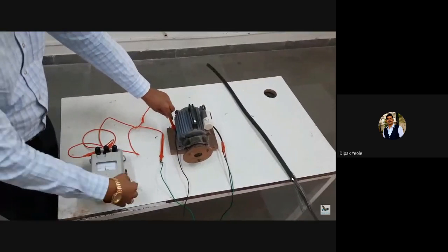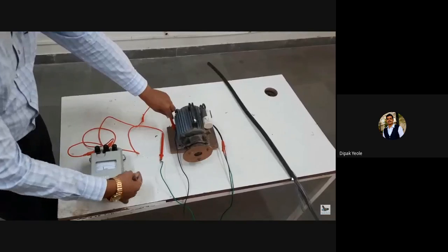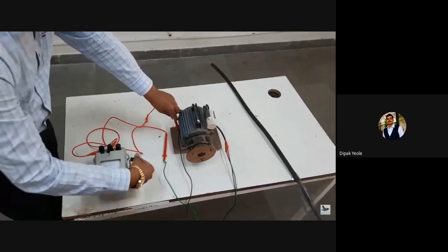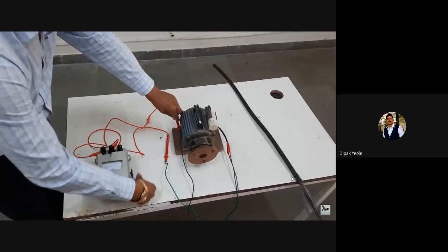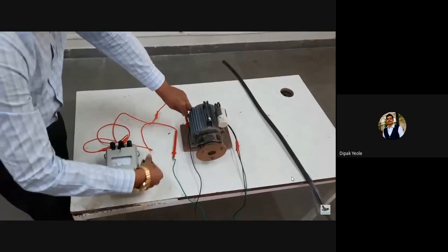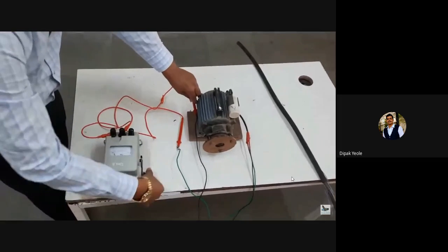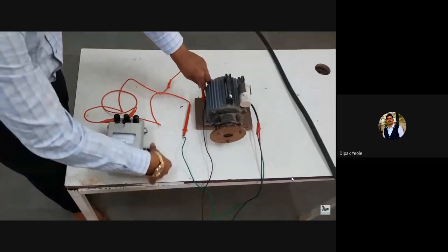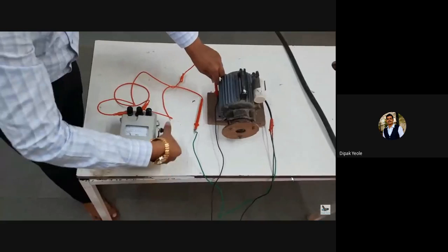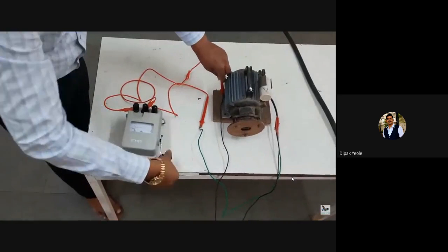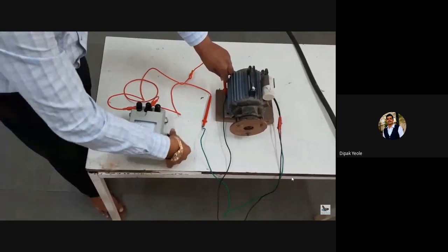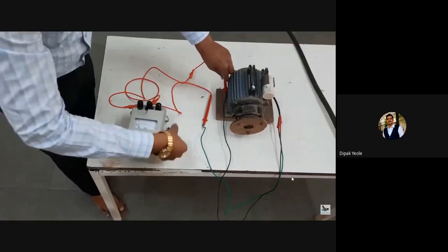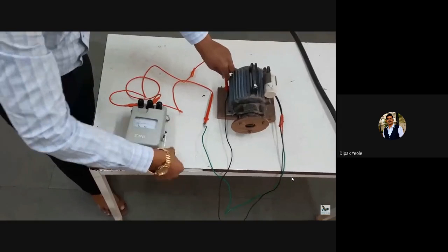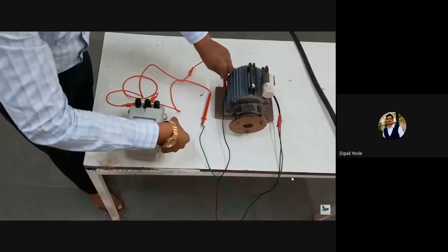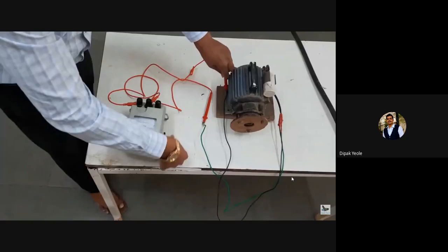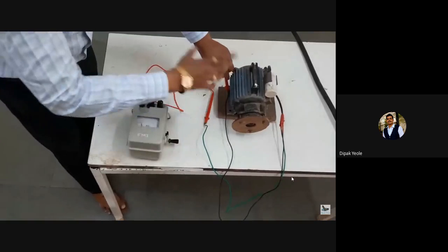We have to rotate this handle, and as we rotate it, we observe a value on this mega ohm meter. You can see the value lies in the range of 200 mega ohm. This is the value we put in our observation table. 200 mega ohm indicates good condition of the insulating material available for our electrical motor.